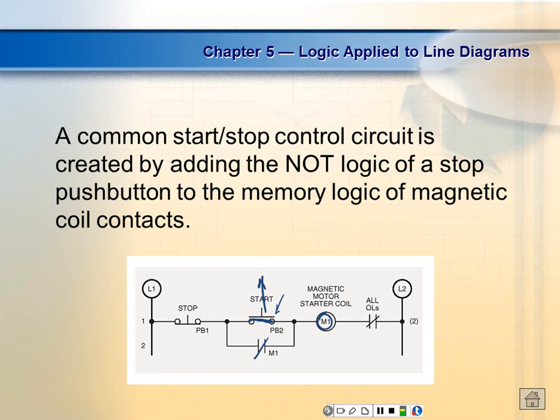So this is in here to protect the motor against overload, right? Your sensors are over in the motor, in the power circuit, but the contact is over in the control circuit. So the overload trips, kicks this out, causes M1 to drop out. If M1 de-energizes, it opens this contact. Now we've lost this, right?